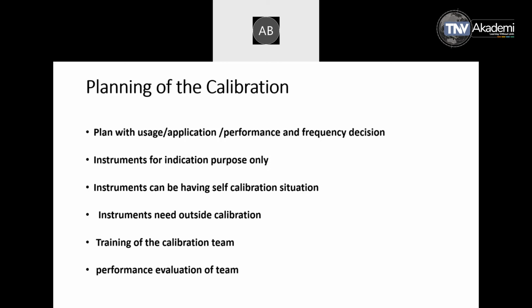So all this was discussed, and later the thought came that a few instruments can be there for indication purposes only. Some of the temperature indicators, some of the humidity indicators, some of the pressure gauges, they are not adding anything to the quality of the product and process. They are just there to show that yes, they are operating, and the parameters are for indication purposes only. So there are some instruments which may not need to be brought under a calibration scheme or performance traceability stage. They are only for indication purposes.